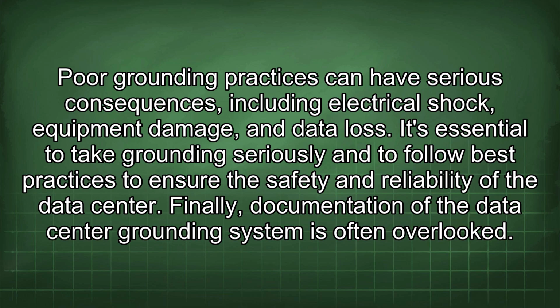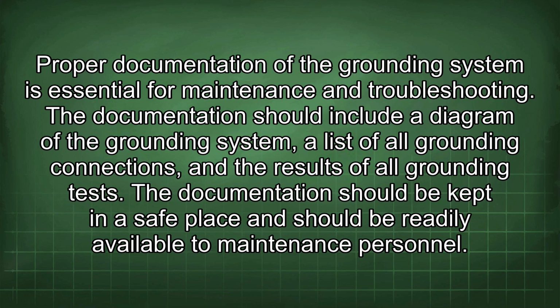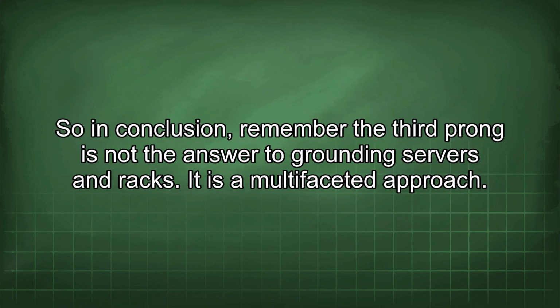Finally, documentation of the data center grounding system is often overlooked. Proper documentation of the grounding system is essential for maintenance and troubleshooting. The documentation should include a diagram of the grounding system, a list of all grounding connections, and the results of all grounding tests. The documentation should be kept in a safe place and should be readily available to maintenance personnel. So, in conclusion, remember the third prong is not the answer to grounding servers and racks. It is a multifaceted approach.